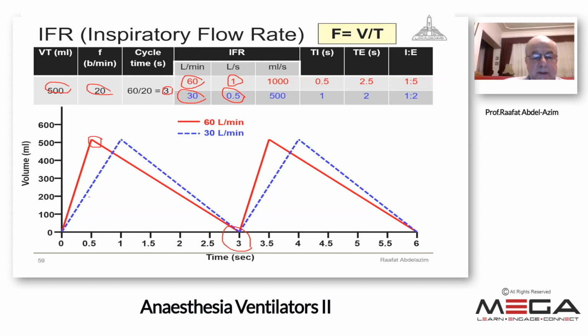Instead of being half second, it will be 1 second. In the first example, the red line, the inspiratory time is half second and the expiratory time is 2.5. It is the same rate of 20, but in the first example, the inspiratory time is half second, the expiratory time is 2.5, so the ratio is 1 to 5.